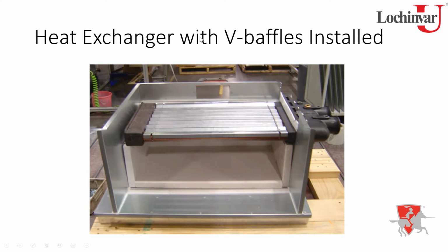I'm not saying this is a normal thing, but if you do feel like you need to pressure wash it or something, just make sure you remove it from the chamber itself and get it away from the unit. Also, sometimes we do get the question, can you use any type of cleaning solution or anything like that? Well, we haven't tested or approved anything here at the factory, but here's the deal. If you need to remove it and pressure wash it and you want to run some type of solution cleaner over it, you can do that. But just make sure it's safe on copper and copper nickel if you have that option. So just make sure you're running something clean on that. And I'd always recommend not leaving that solution on there. Make sure you wash it off before you put it back into the combustion chamber.